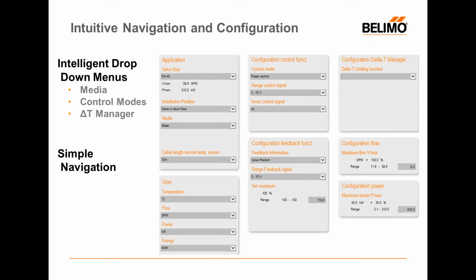At the top middle we see our control mode functionality, which is configuration control function, and we can select position control, which would be our standard pressure dependent valve functionality, flow control, which is the most standard, and that is pressure independent functionality. The valve is looking at the flow meter reading, comparing it to the DDC input signal, and making sure we maintain a specific flow rate, and then another function called power control.